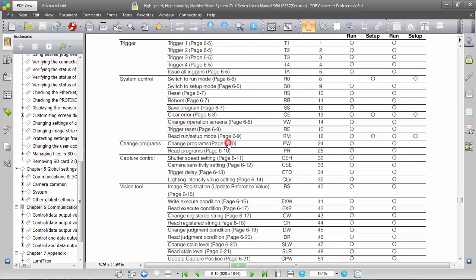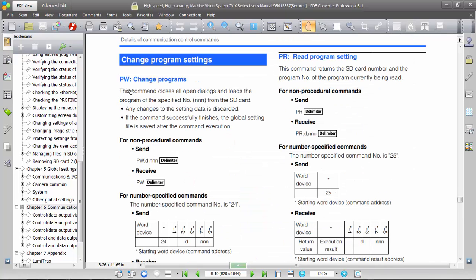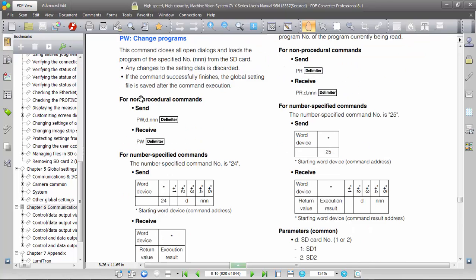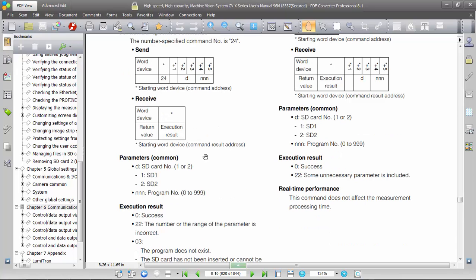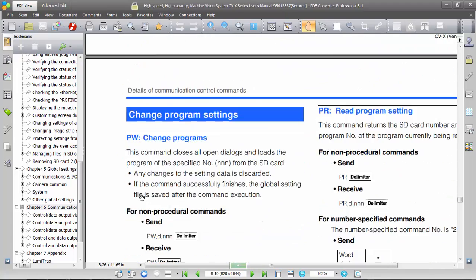Jumping to the PW command, which is generically known as the change programs command — it's command 24. You can see it outlines the command parameters that are necessary. For this one we need command 24 and then two command parameters: the first is the SD card number, one or two, and the second command parameter is the program we want to switch to. Refer to this section for all the details of the commands.